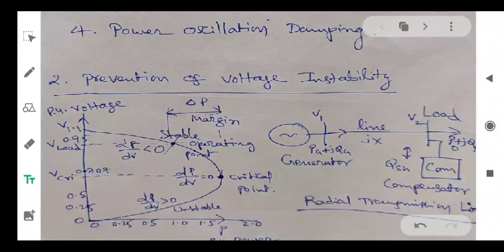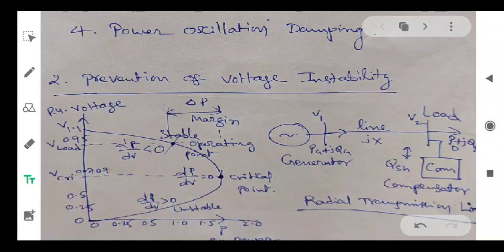Voltage stability improvement is explained by a system comprising of a single generator feeding the load through a transmission line. It has two buses — bus 1 and bus 2 respectively. Bus 1 is connected to the generator and bus 2 is connected to the load. The best location of the compensator is at bus 2, that is at the load bus.